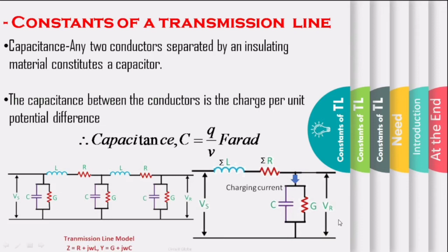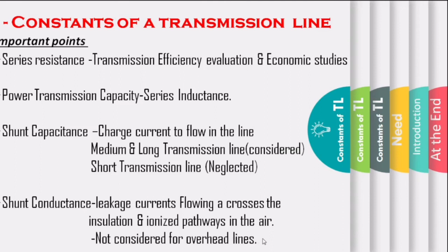Important points regarding the constants of a transmission line: series resistance is very important in transmission efficiency evaluation and economic studies. Power transmission capacity of a line is mainly governed by the series inductance. Shunt capacitance causes a charging current to flow in the line and assumes importance in medium and long lines; for short transmission lines, shunt capacitance is neglected. Shunt conductance accounts for leakage currents flowing across the insulators and ionized pathways in the air, and is not considered for overhead transmission lines.